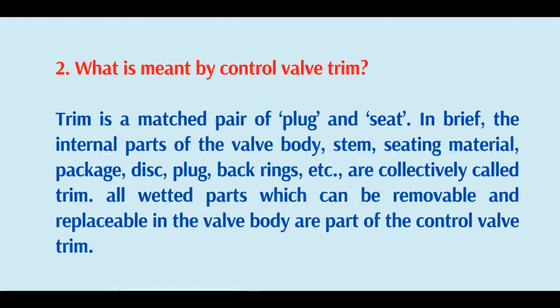What is meant by control valve trim? Trim is a matched pair of plug and seat. The internal parts of the valve body — stem, seating material, package disc, plug, back rings, etc. — are collectively called the trim. All wetted parts which can be removable and replaceable in the valve body are part of the control valve trim.